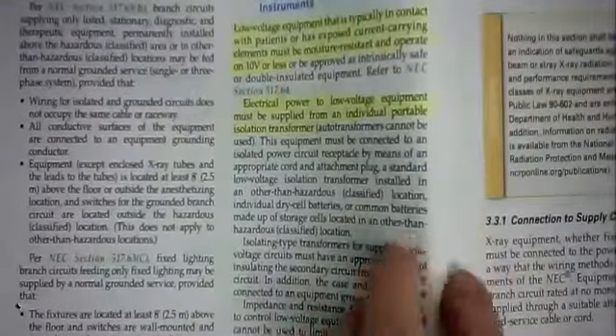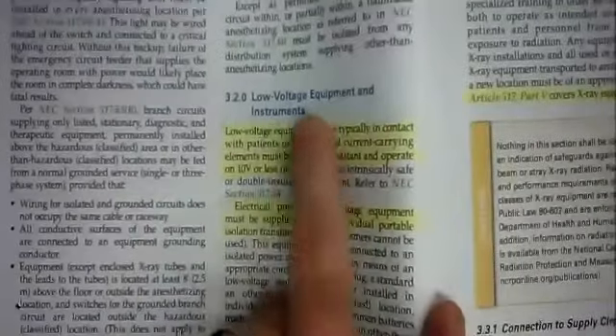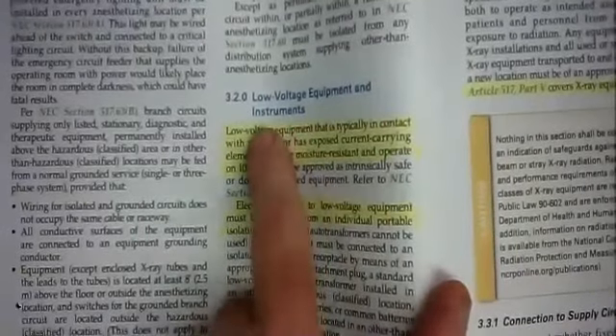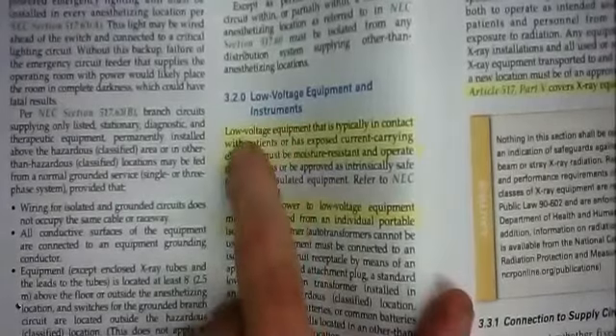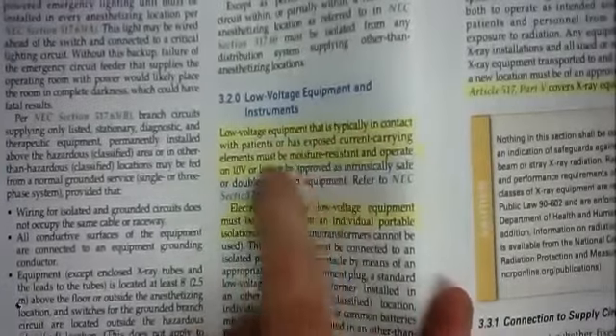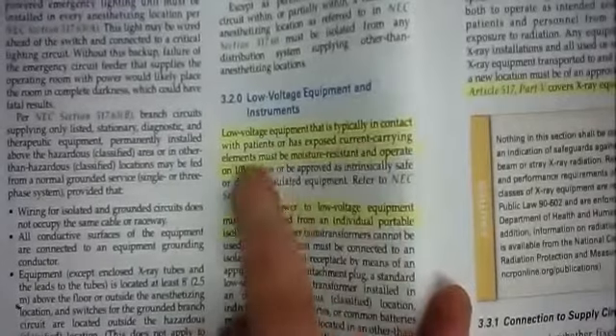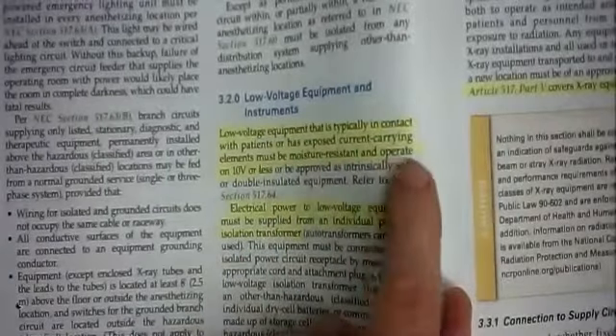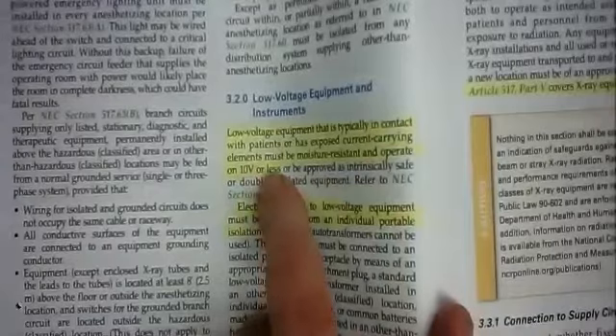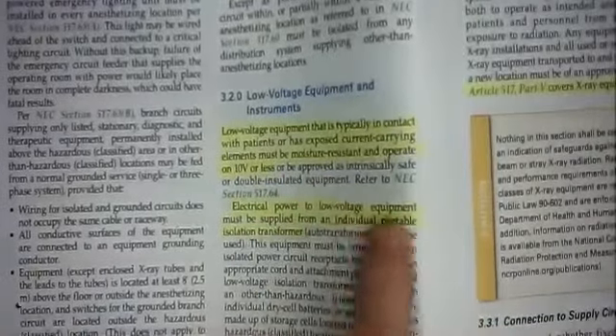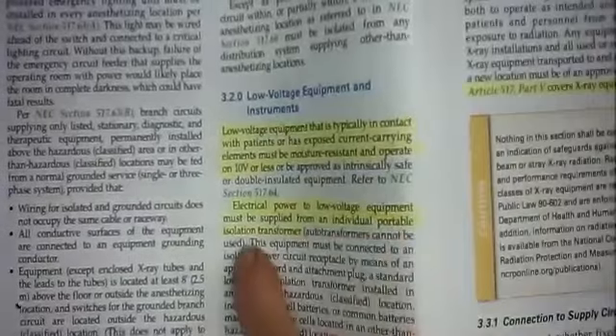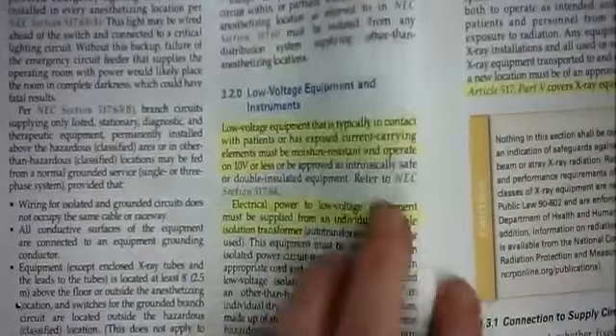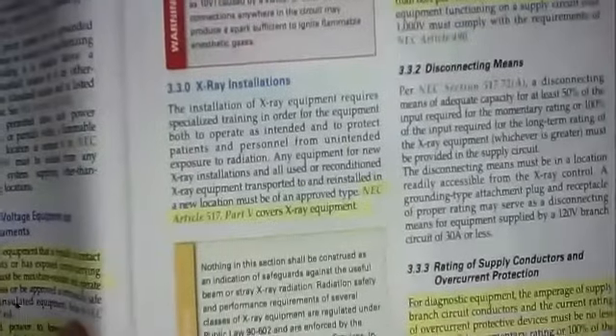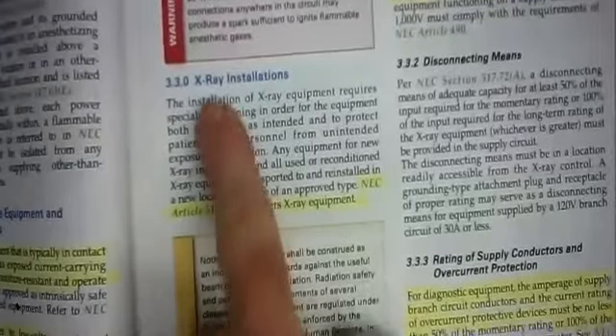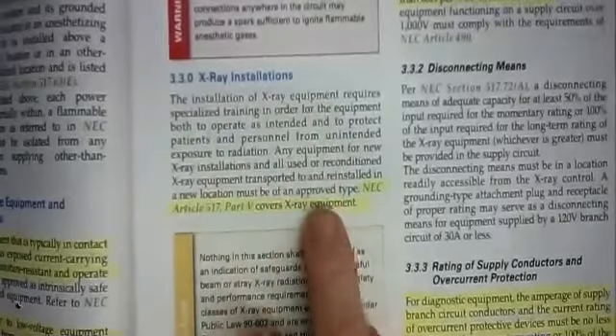Okay. On page 20, on the right-hand side, low voltage equipment and instruments. Low voltage does not mean low hazard. Low voltage equipment that's typically in contact with patients or has exposed current carrying elements must be moisture resistant and operate on 10 volts or less. Electrical power to low voltage equipment must be supplied from an individual portable isolation transformer, isolating the primary from the secondary.